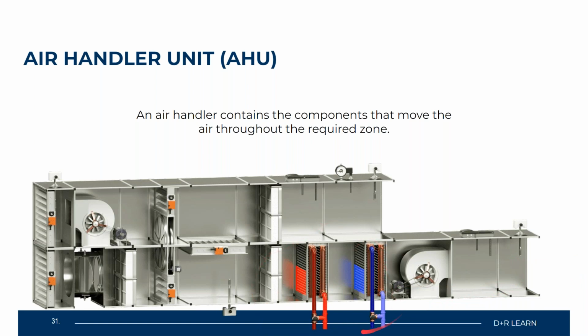The same operation will happen when you have your cooling. You will have the chiller system, which we spoke about earlier, send that chilled water over to the chilled water coil, and when this fan comes online, it's going to draw air across that 44-degree coil. Typically you'll have an estimate of about 175-degree water sitting in this heat exchanger or coil here.